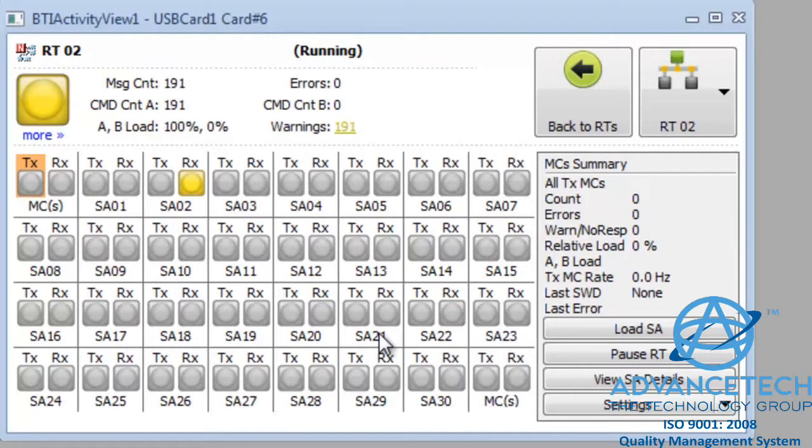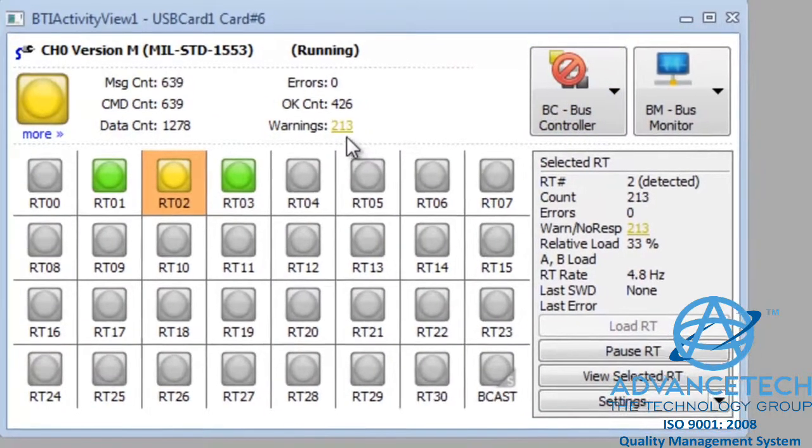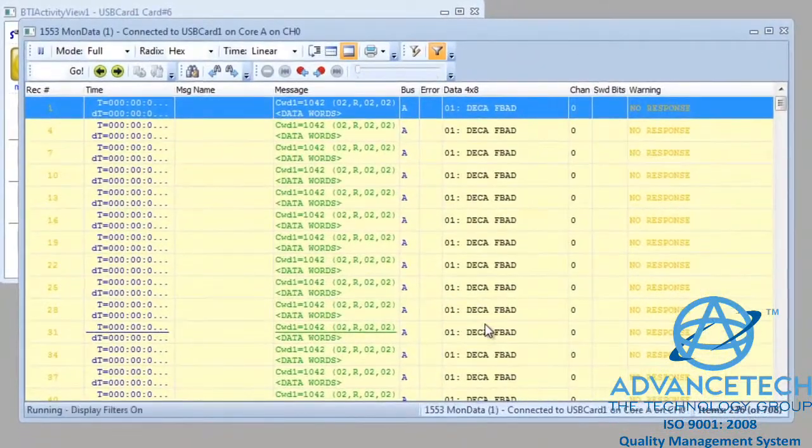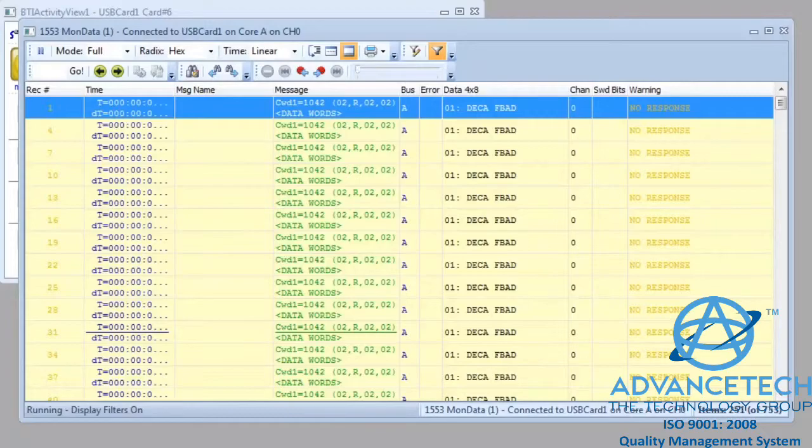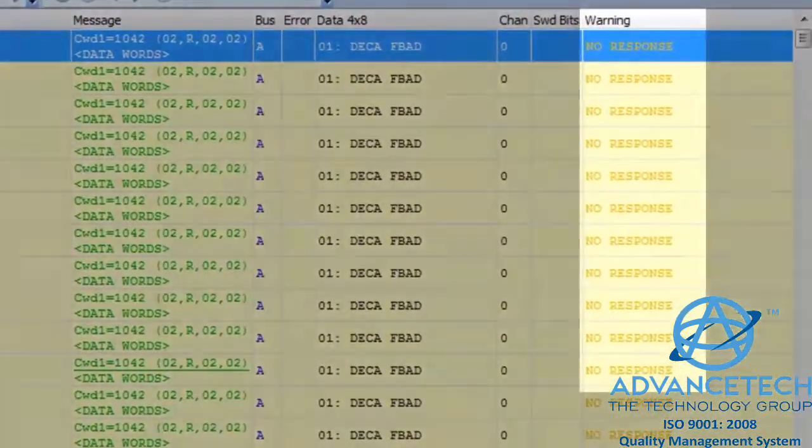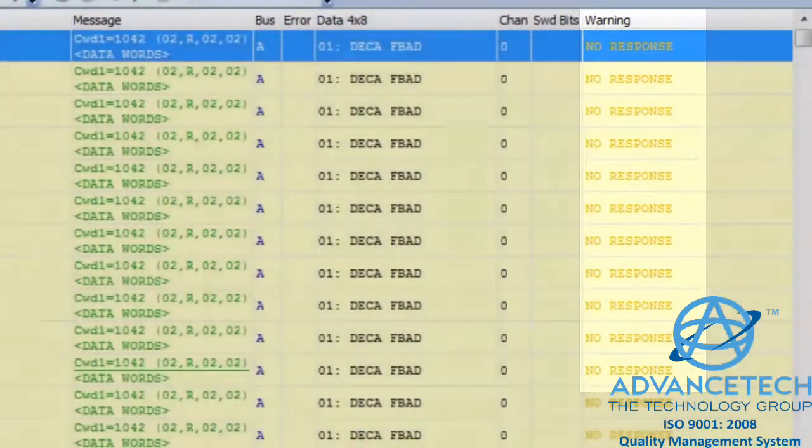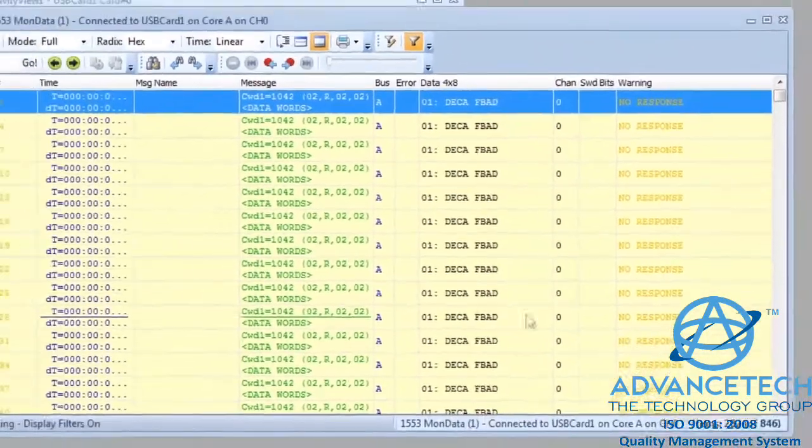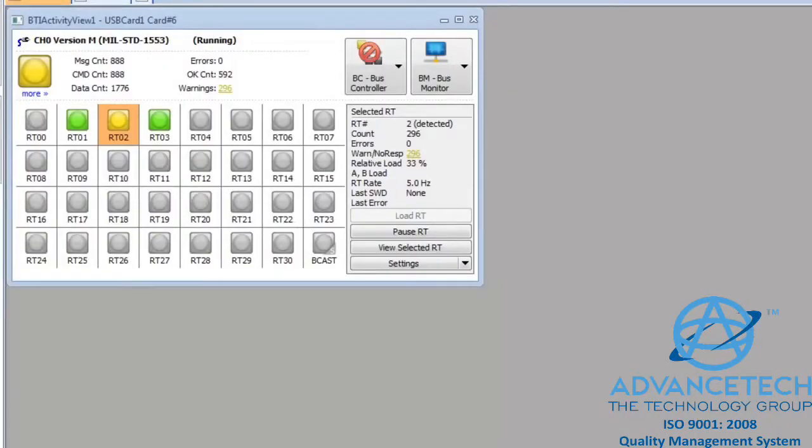So let's click the Back to RTs button to return to the top level, and click on the Warnings count above the icons to view the log of data. The data log is showing us that every message to this RT is resulting in a 1553 no response. So we have some sort of an external problem here. The RT is not responding.